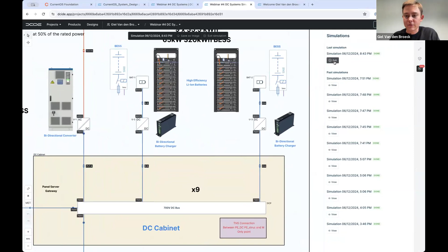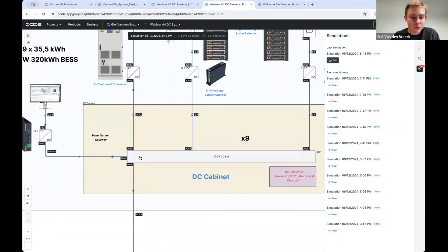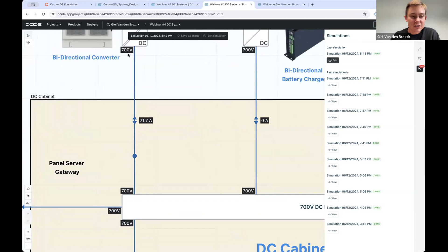And now you can visualize how the power flows into the system. There's about 72.5 amps drawn from the three-phase AC grid at 400 volts. The DC bus is maintained at 700 volt DC, with 71.7 amps flowing to your DC bus. There's a little bit of current flowing to power the 24 volt auxiliaries on the left-hand side, and of course the majority of the current is used to power these 11 kW EV chargers in the system.